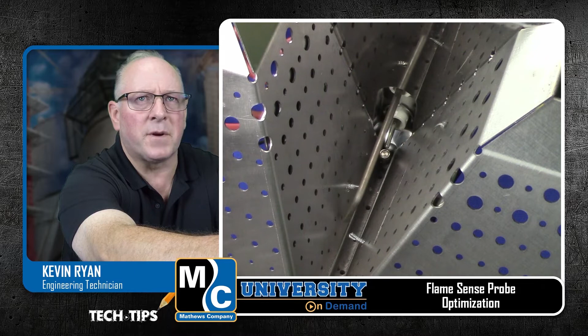So if we could take a look at the burner itself right now, I'm going to show you a couple of the problems that we've seen. One of which is the flame sense probe, which is on the top here. I'm going to move that so you can see it—this right here, that senses flame.